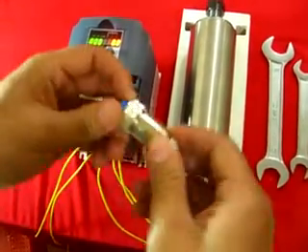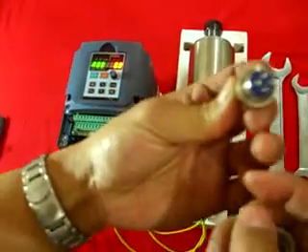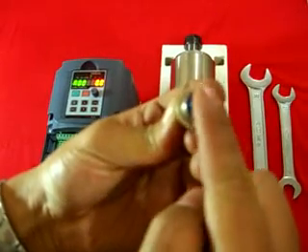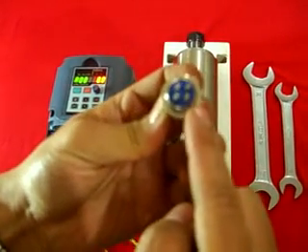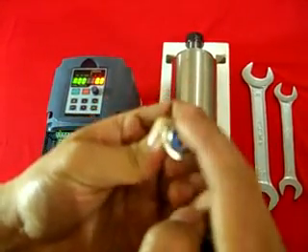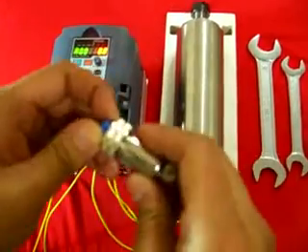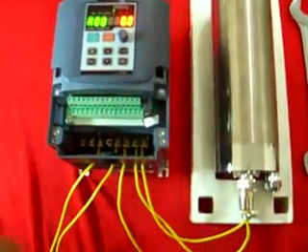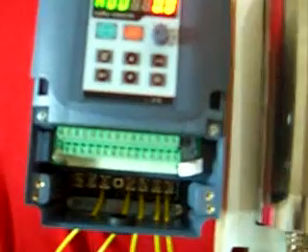In here you can see there's one, two, three, four wires. We just connect to one, two, three. The fourth one is for the ground. Then connect one, two, three, and then come here you connect U, V, W. These two wires are for 220 volt single phase.